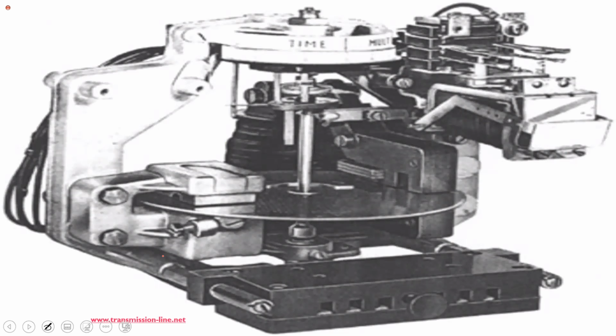For your watt-hour meter, you have your turning disc. The principle is that you have fluxes which are superimposed on this disc. One flux is as a result of the current, and one as a result of the voltage. So you have the voltage producing a current, which produces a flux, which is superimposed on the disc. And the current also produces a flux that is superimposed. And then, of course, they cause the disc to turn.